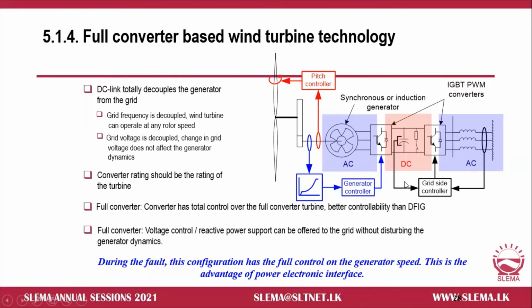This has a bigger advantage of decoupling the wind generator operation from the grid operation by a DC link capacitor, so the only coupling is power. We can even put a small battery energy storage if we have more resources to build this technology with more facility. Or because of the decoupling, we can bring down the speed of the generator much lower, so power extraction at lower speed is also possible.